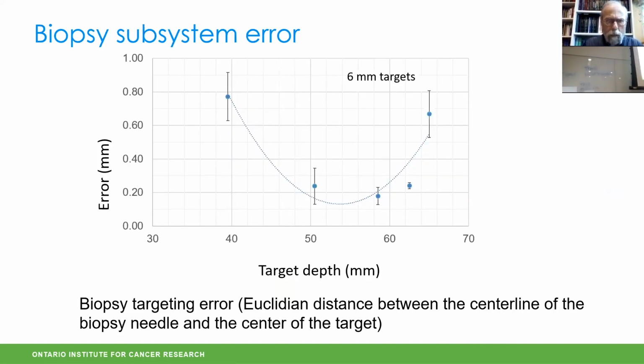We show the accuracy of our biopsy guidance system, where we plotted the error in millimeters on the vertical axis and the depth of the lesion ranging from 4 centimeters to about 6.5 centimeters. So you can see the error in guiding a needle to the target is about 0.2 to about 0.8 millimeters. So that's in fact quite good. Of course, these are under optimal conditions. There's no movement, no breathing. It's a static phantom under idealized conditions. So we don't think we can do better than that, but of course we have to build a complete system and see how all the errors and the mechanisms propagate to give us the final error.